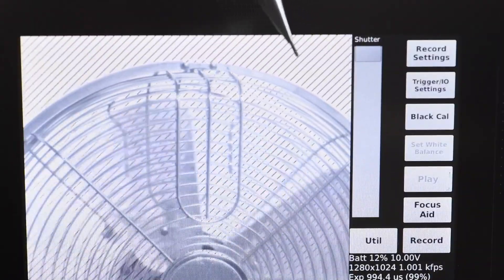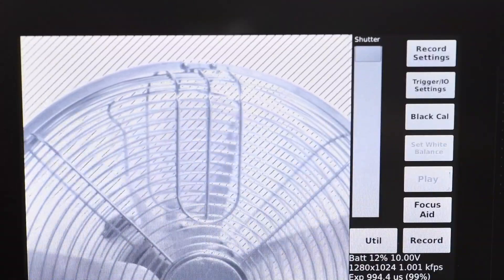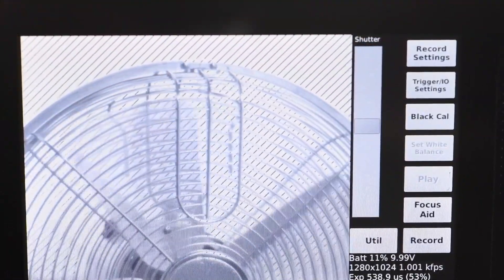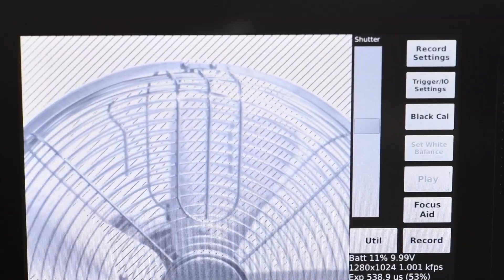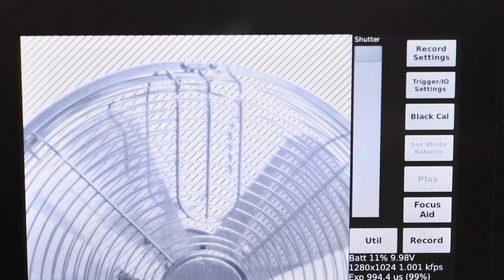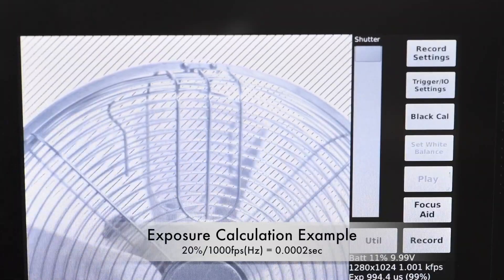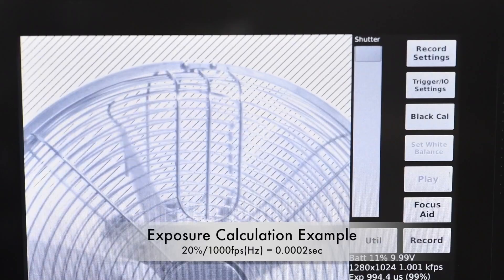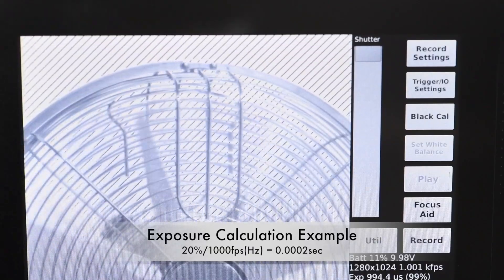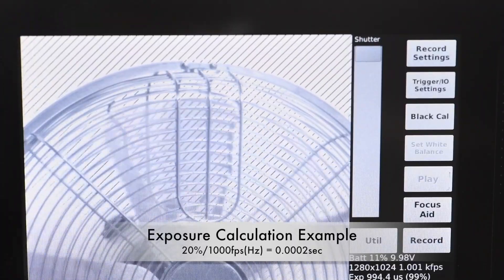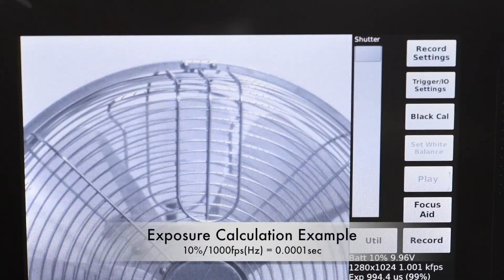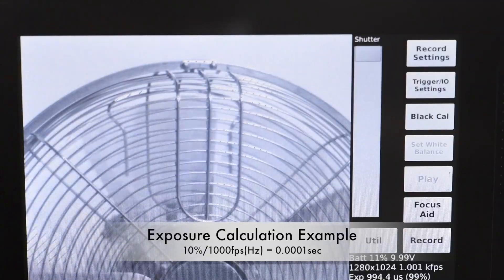You can see that we have some zebra lines here — it shows that we're overexposed. Notice my exposure here reads 994 microseconds, and whenever I try to change the exposure on the camera it does nothing, because the exposure is controlled by the signal generator. Right now I have the signal generator set for 20% duty cycle, which would be 0.0002 seconds for an exposure. I'm going to change that down to a 10% duty cycle — and as you can see, that change just remedied the zebra lines and the overexposure.